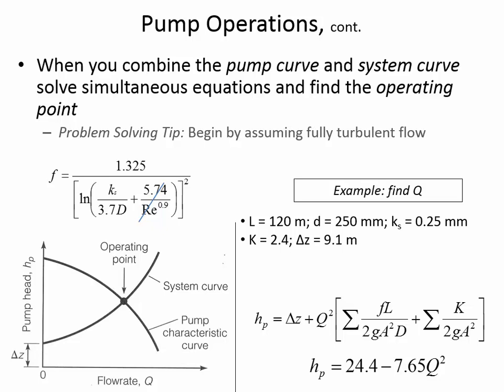Okay, so 9.1 plus 249.74 q squared is equal to 24.4 minus 7.65 q squared. Okay, we'll combine the q's together. It's 257.39 q squared is equal to 15.3. Solve for q. Q equals 0.244 cubic meters per second. So that's the flow rate in the system.